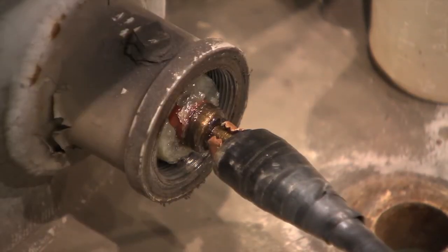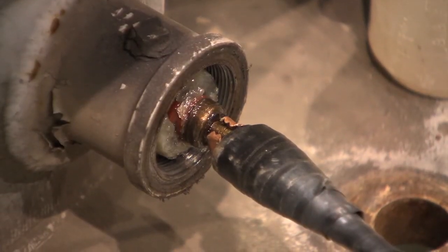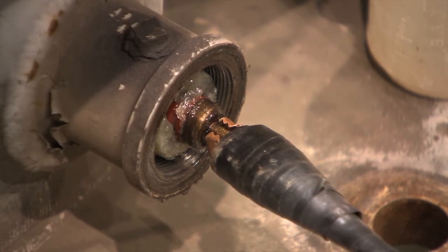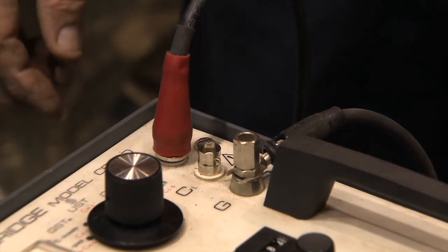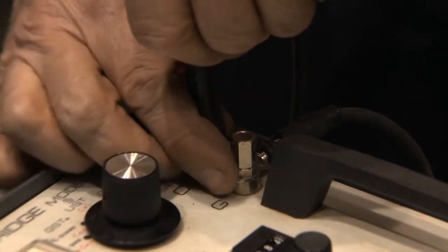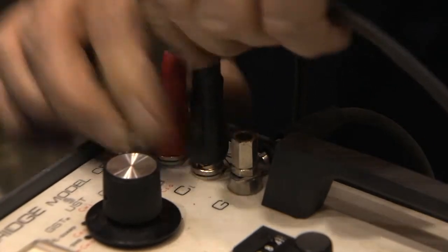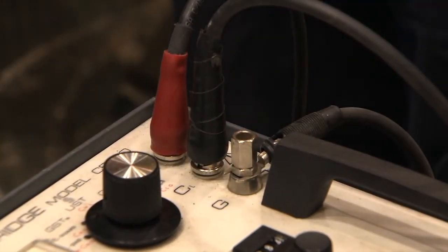Connect one end of the low voltage cable, the black lead, to the capacitance cap. Connect the other end of the lead to the terminal labeled C1 on the capacitance and dissipation factor bridge.